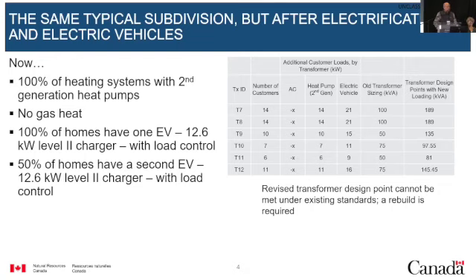That means you get a very large peak on that transformer the more electric vehicles you add. If you take 62 homes and change them to 100% second-generation heat pumps, add one EV with a 12.6 kW level 2 charger with load control, and have 50% of homes with a second EV - which isn't unrealistic, just look at driveways in your neighborhood - the transformer design loading with the new point system gets quite high.